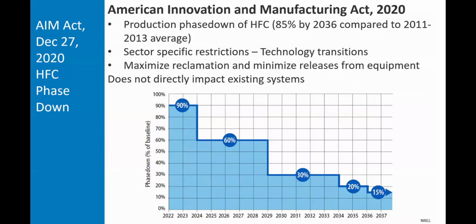So, things that are happening. There are two schedules happening simultaneously, and they're not in sync with each other, because that's how governmental things work or don't work. Starting in 2022, the refrigerants, meaning R410A, 134A, 407C, all those HFCs that we use in our industry, started being phased out. Manufacturers of refrigerant were only allowed to produce 90% of what they used to make back in 2012. The next step down happened last year, where they can only make 60% of what they made 12 years prior. Then it keeps chopping its way down until we finally get to 15% in 2036, and then it stays there at 15%. It doesn't actually go down to zero.